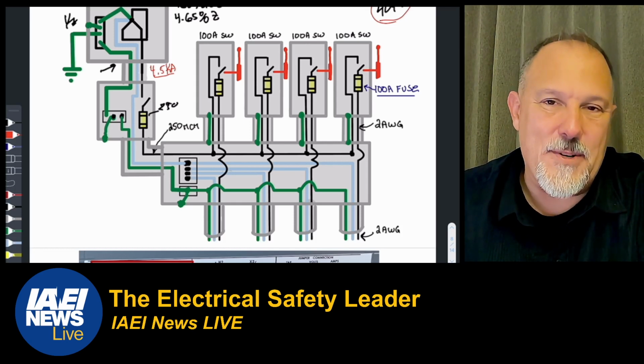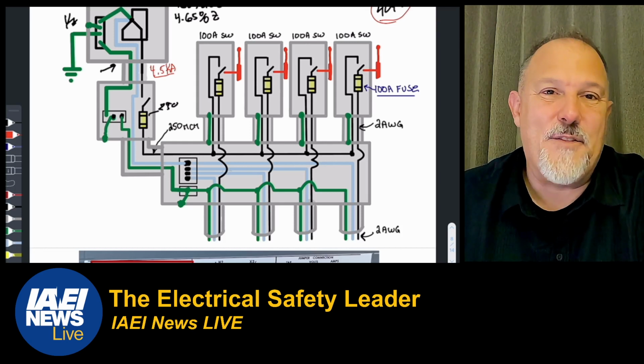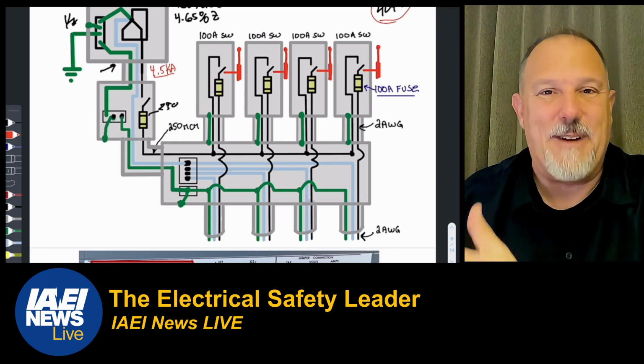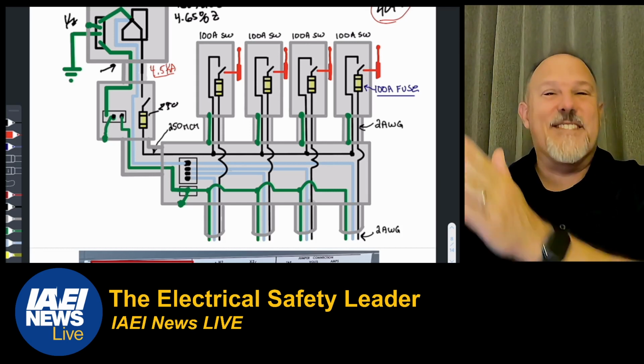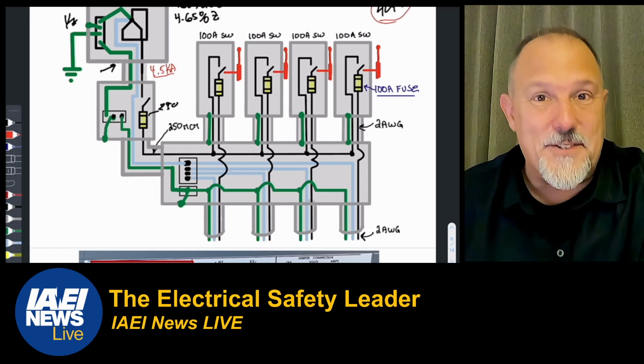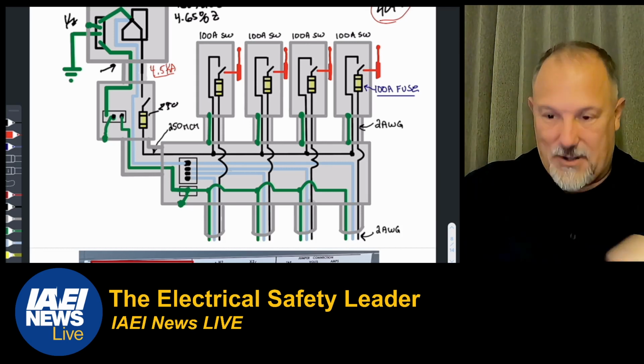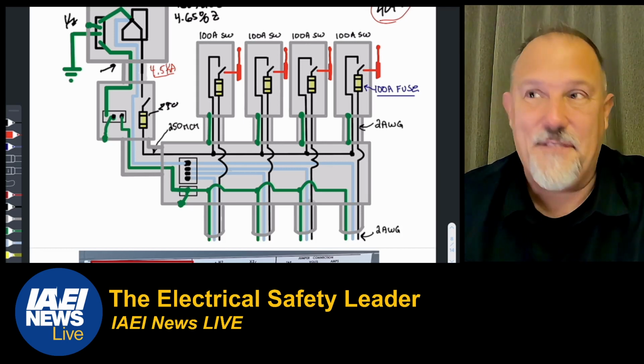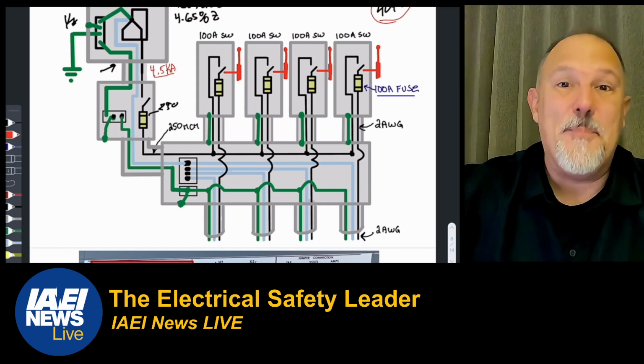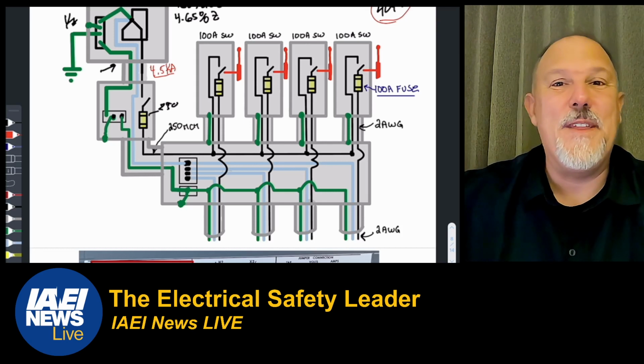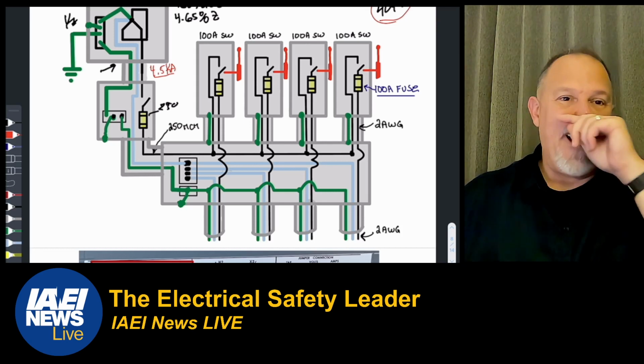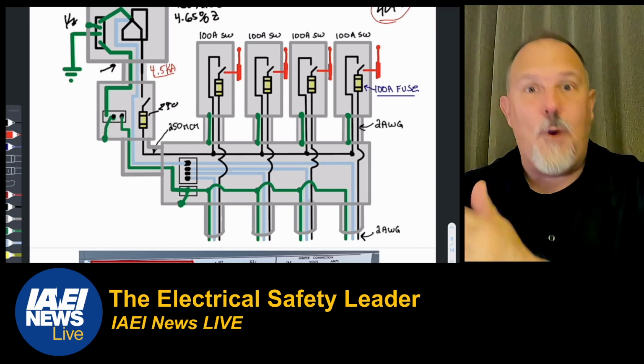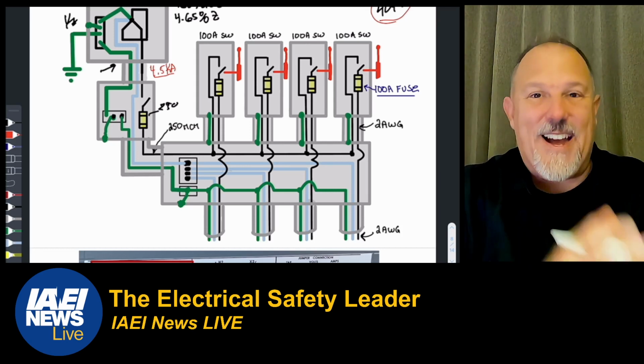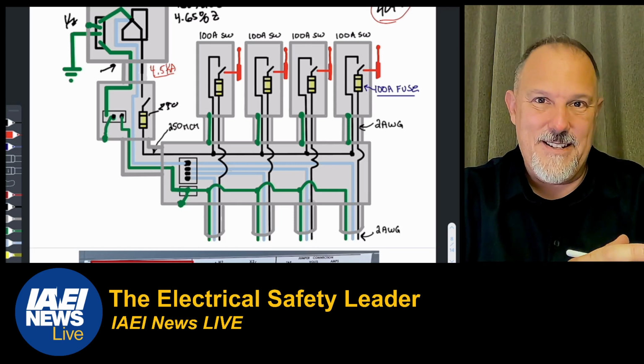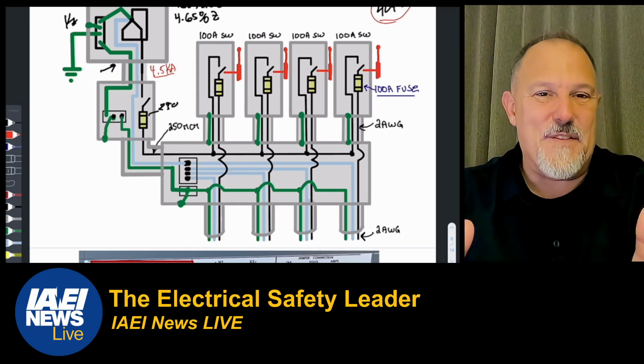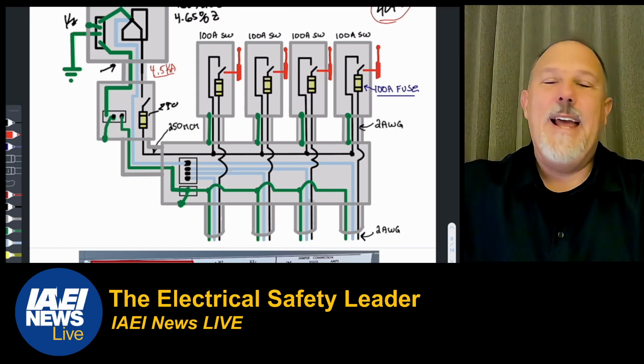I think it's in 422. Check me out. For dryer circuits, you're required to have that neutral, that grounded conductor. Because why? Because of the light that they started putting in dryers. You know, you open the door and there's a little light that comes on and shows you. Well, how are they powering that light if they weren't pulling a neutral to the appliance? They were powering it over the equipment grounding conductor. And although it wasn't GFCI protected back then, if it was, it would have been tripping GFCIs left and right. But it was violating Article 250. Okay, this is the cool stuff about the code. This is what you learn at these meetings.